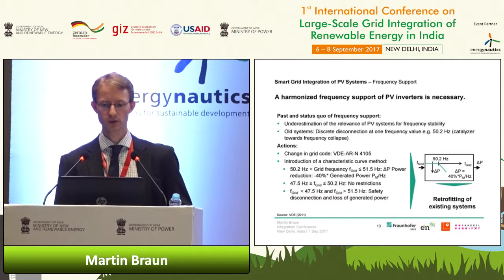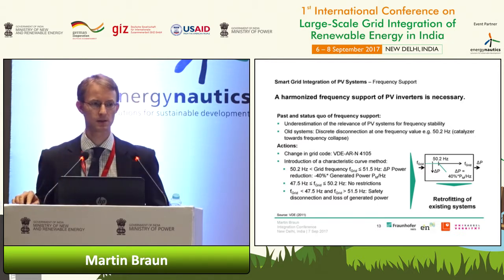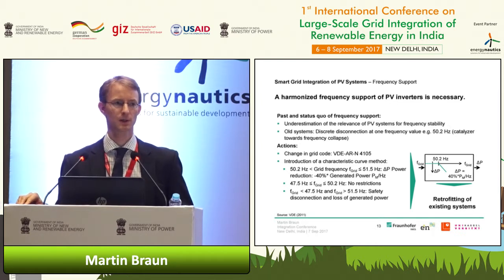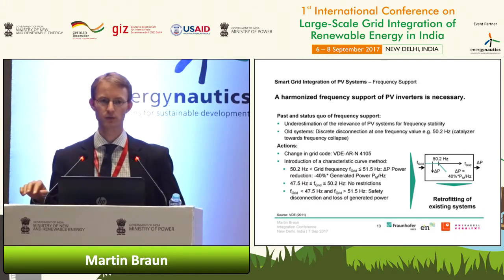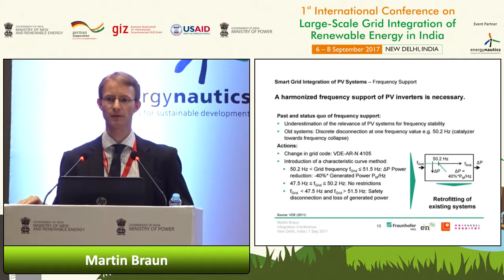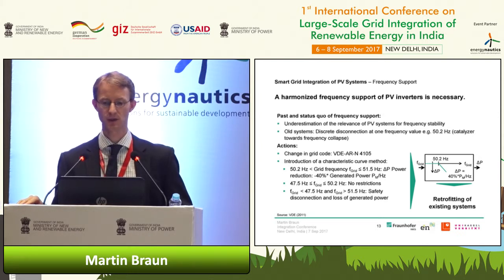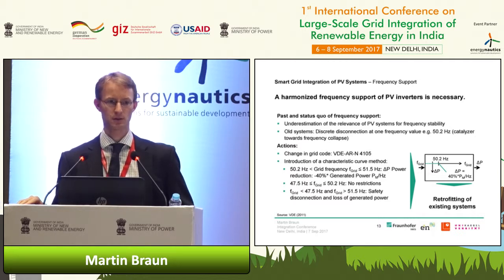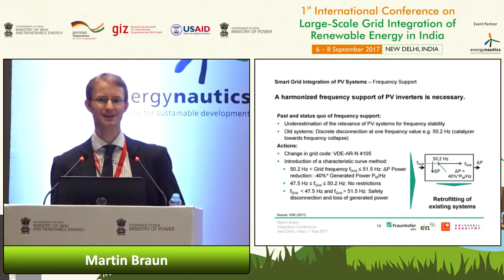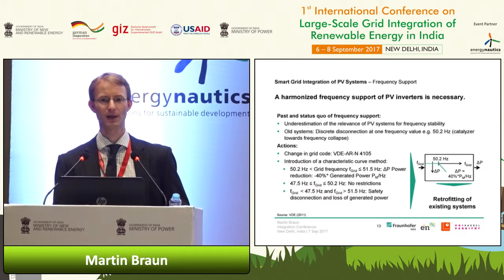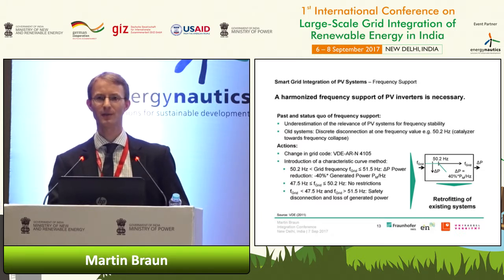Starting with the frequency support scheme - you heard yesterday about the 50.2 hertz problem. Inverters were getting parameters for over-frequency protection that were not oriented on stability, but on the assumption we didn't have sufficient PV systems for it to be a danger - but it was underestimated. There was a huge retrofitting action costing hundreds of millions of euros, and hundreds of thousands of PV systems had to be retrofitted. This was a mistake - please don't do it again. Ensure your renewable energies stay connected to the grid even in under-frequency situations, and that in over-frequency situations they're not disconnected but dynamically decreasing, thereby supporting frequency stability.